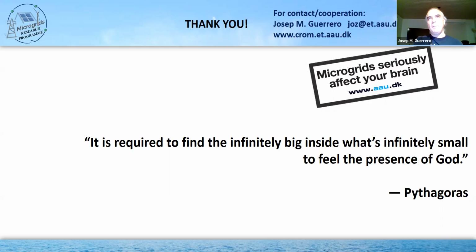But this can be done in a very autonomous way. If the ones injecting power to the AC side have frequency regulation, like in photovoltaic systems as I presented today, if the frequency goes very high, the power will inherently go down, so the system regulates automatically. The same happens on the DC side: the DC converters sense the DC voltage all the time, and if it goes very high, they automatically reduce the power. That's the role of the interlink converters.